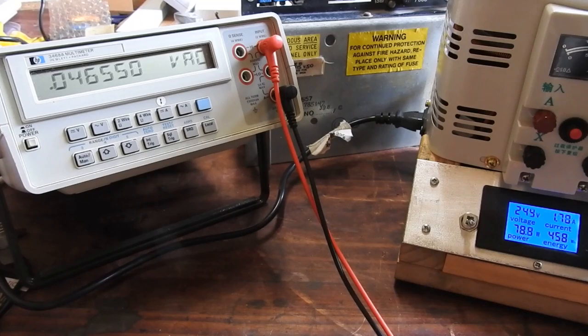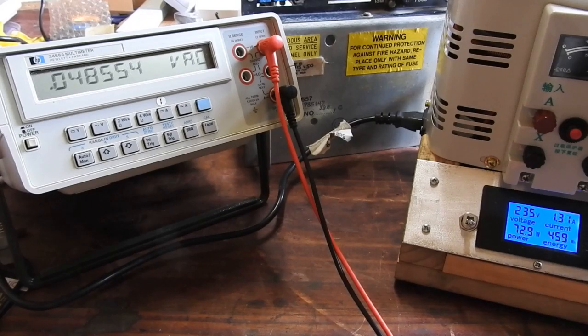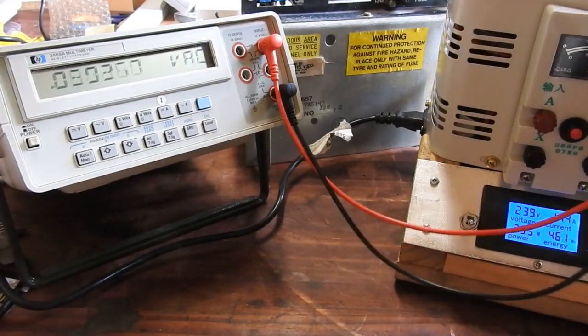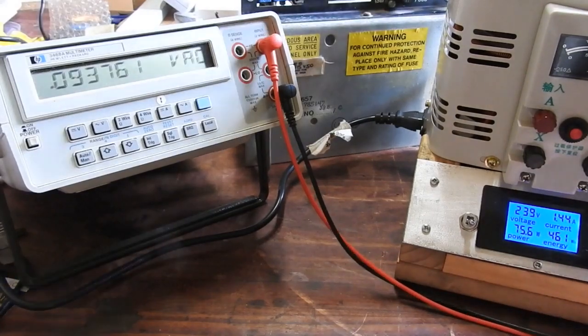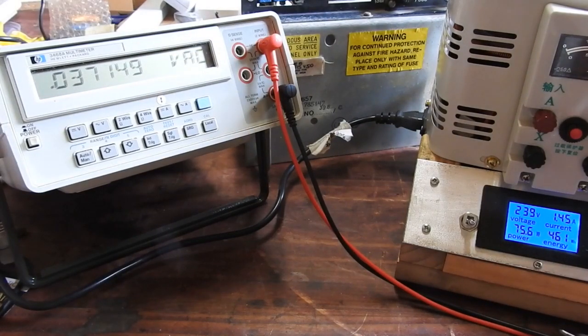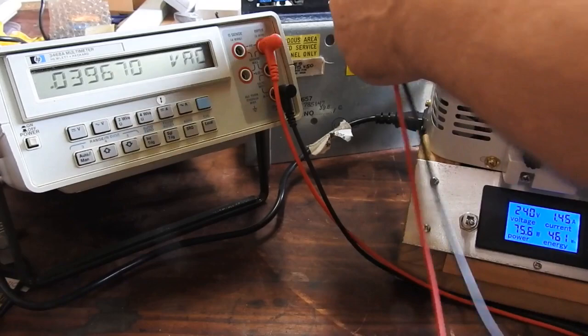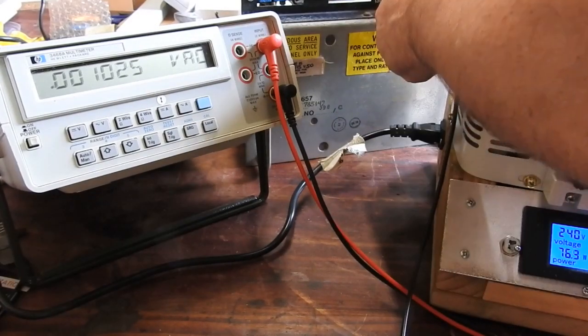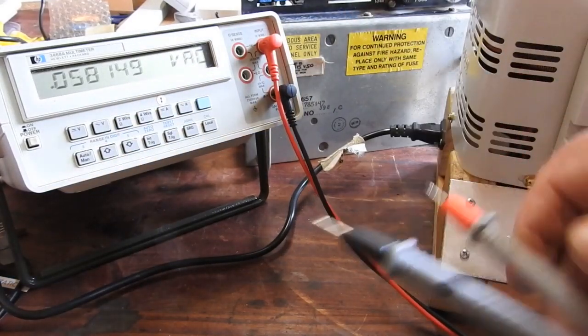So the current is going up a lot once we get to 240 ish. What should I assume, 240 volts is supposed to be the nominal it was back in the 80s when this thing was installed. Just for interest what's coming out of the, well that actually that Point 4 might not be a winding it might be a thermal switch or something inside the transformer to indicate when it's getting too bloody hot, there's no voltage there, it must be a switch or a thermistor or something.